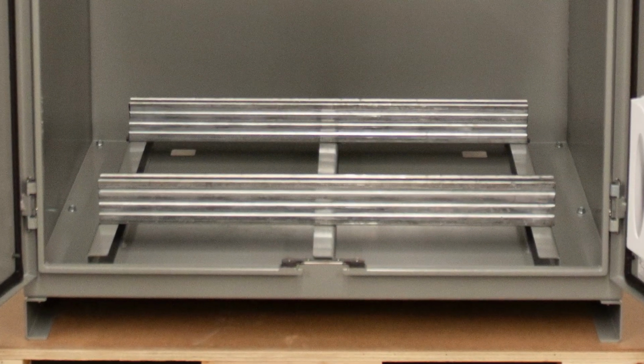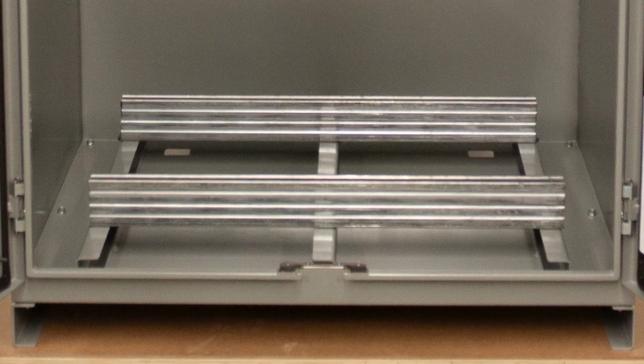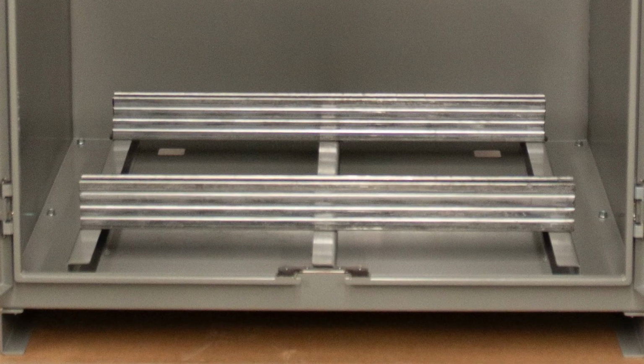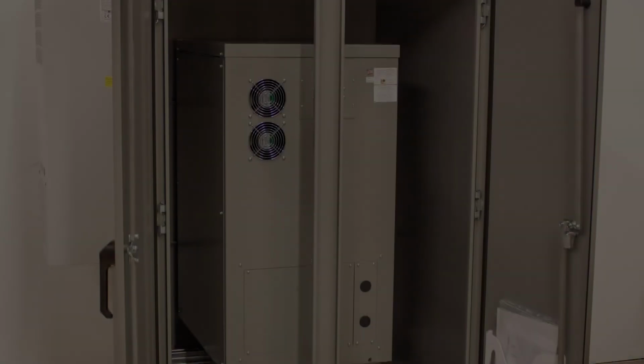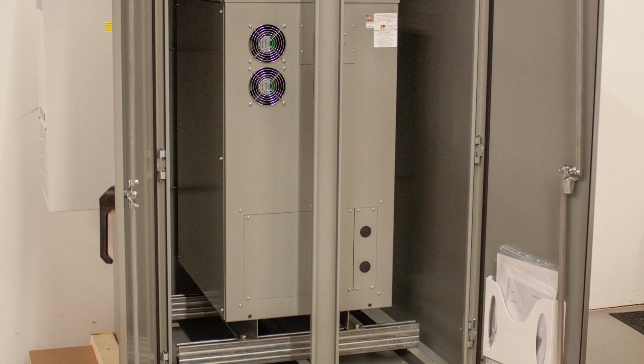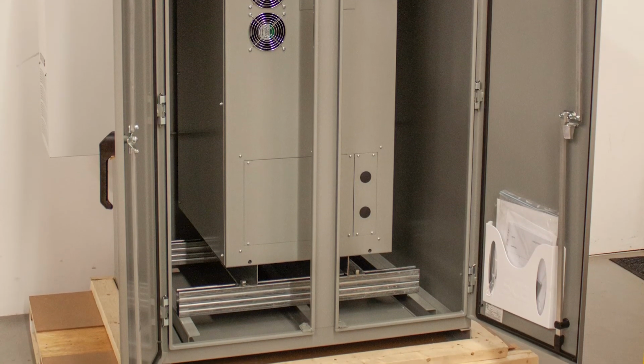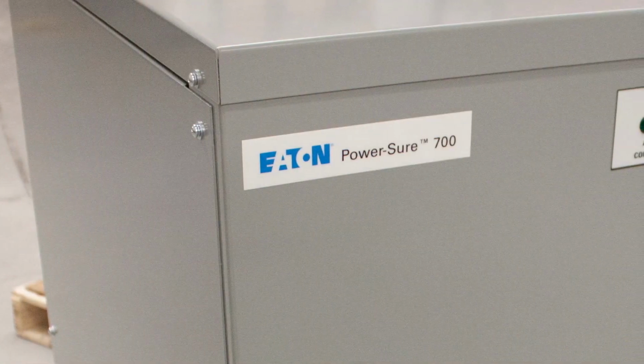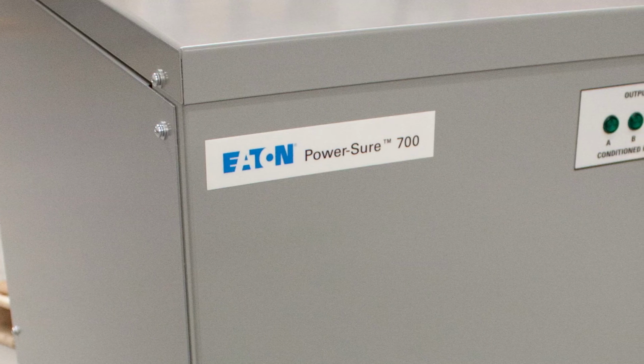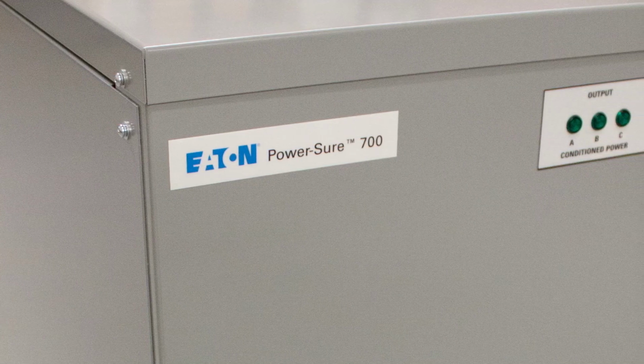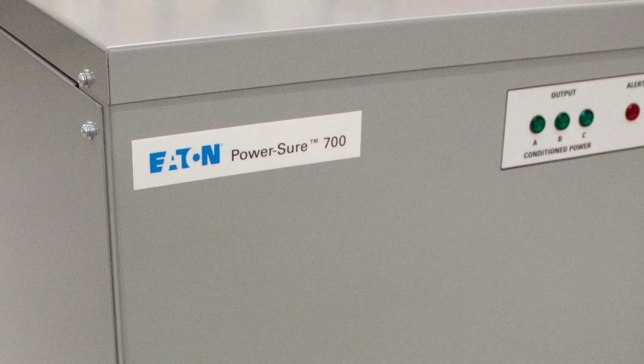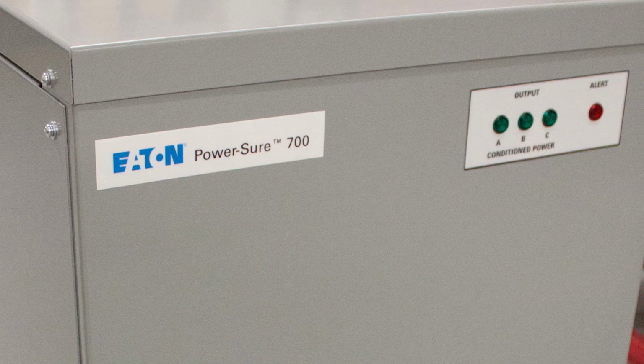A mounting frame assembly was cut to measure and bolted to the enclosure base through the bottom and C-channel leg stands. A 25 kVA power conditioner was installed and secured to the mounting frame assembly. The Eaton PowerSure 700 provides voltage regulation with a transformer and filter to remove transients and noise from the electrical circuit feeding sensitive components like PLCs.